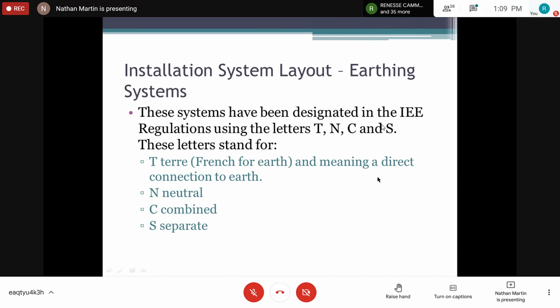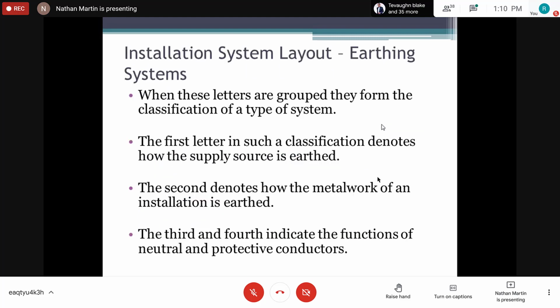Now we said T is terre in this sense, meaning a direct connection to earth. So once the code has a T in it, we are saying that there is a direct connection to the mass of earth, right? Once we see N, we have a neutral, and when we see C, there's a combined combination. Where we look at the combination S, there's a separate earth provided, right? When these letters are grouped, they form the classification of a type of system.